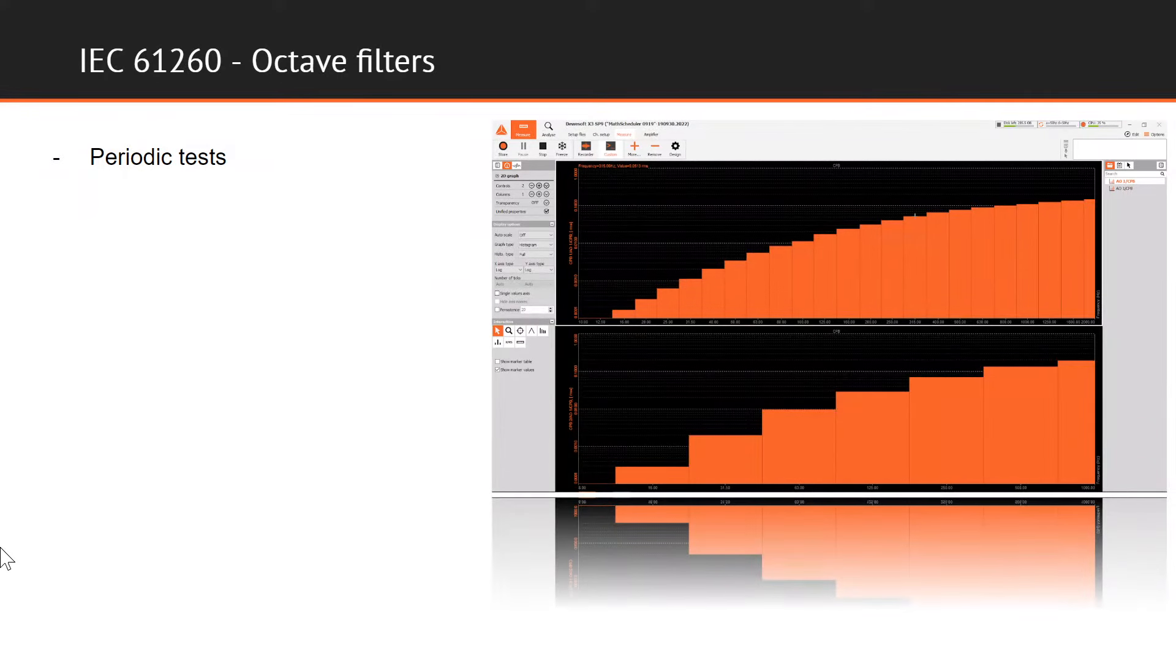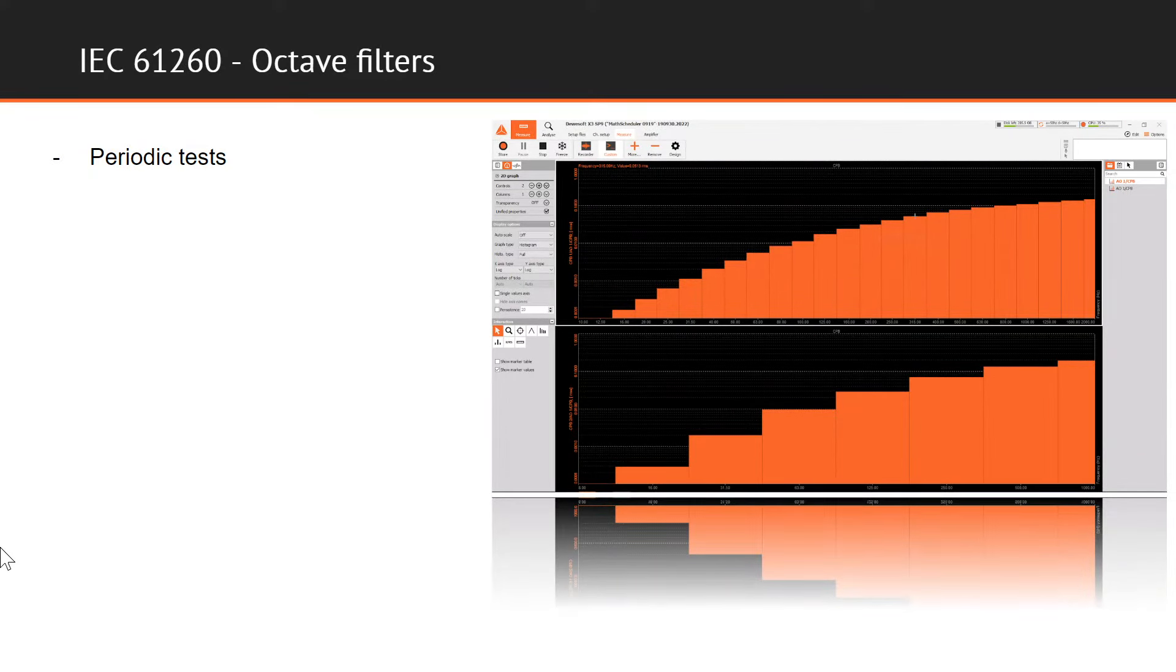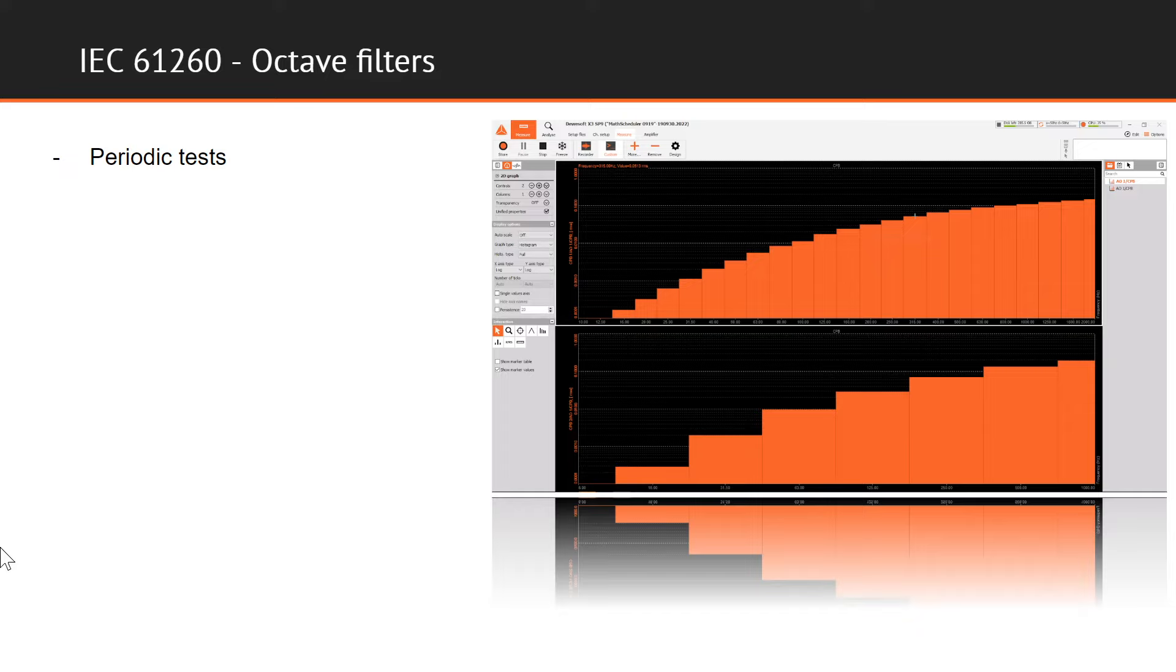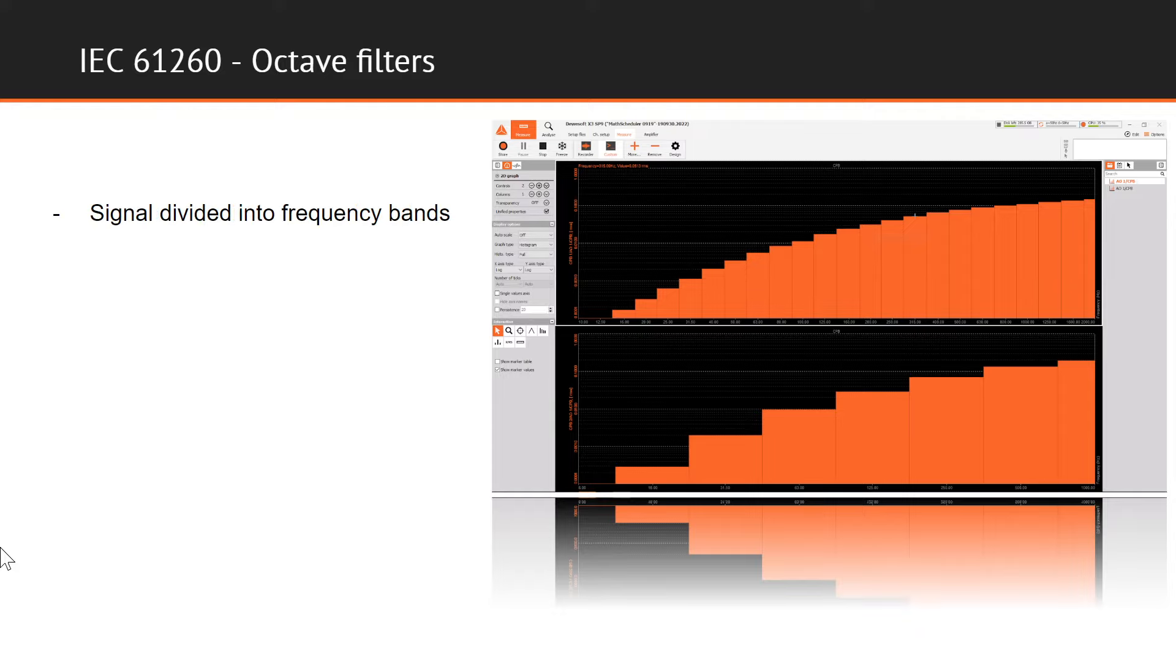We have looked a bit at how sound level meter calibration is performed, so next in range of very often used and required calibrations is calibration of octave and fractional octave filters according to IEC 61260. Periodic tests of octave band and fractional octave band filters, whether as dedicated instruments built in sound level meters or in other measurement solutions, are performed according to standard IEC 61260.